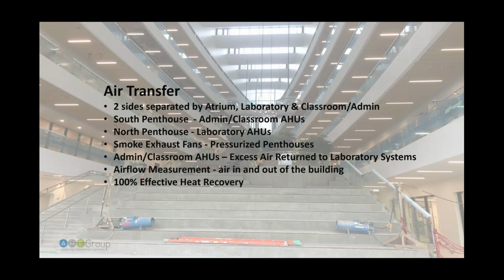Air transfer, I think this has been talked about a decent amount throughout Canadian projects. And so if you ever get a chance to look at reusing office or administrative air into your lab systems, it's really one of the best ways to recover heat in a laboratory. When we look at air changes in labs, I think we sometimes get stuck on the idea that it needs to be 100% outside air, but we all just need to remember that those air changes are really looking for clean air. And ASHRAE 62 is still identifying how much outside air we need in a lab. And so typically that's going to be a lot lower than the 8, 10, 12 air changes that labs typically are going to be operating at.